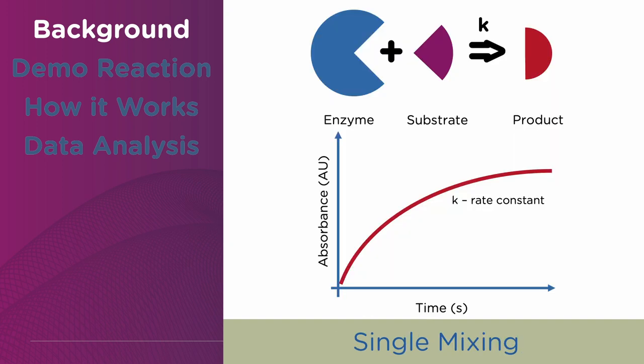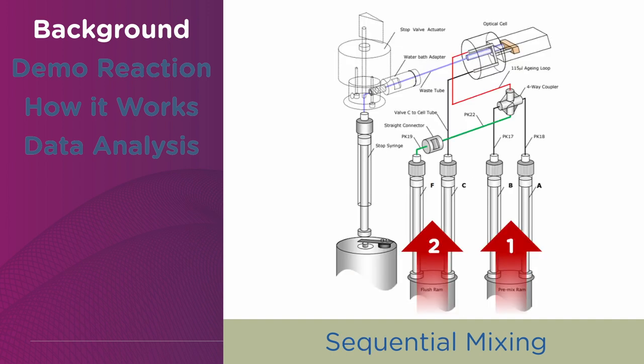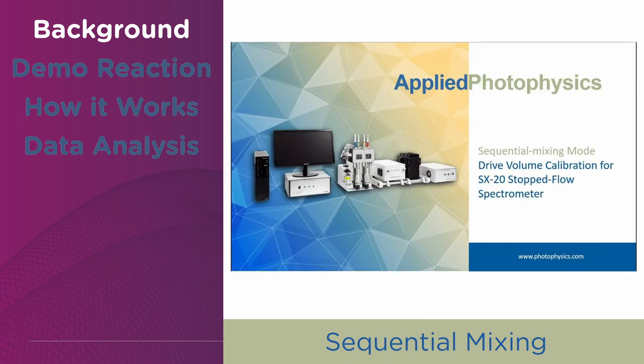Single mixing implies mixing an enzyme in one syringe and a substrate in the other, and observing an optical change as a function of time as the substrate is converted into the product. Sequential mixing, or mixing of three reagents, is also supported on our instrument. We have made a video demonstrating how to switch from single to sequential mode on SX-20, which you can check by clicking the link in the video description.